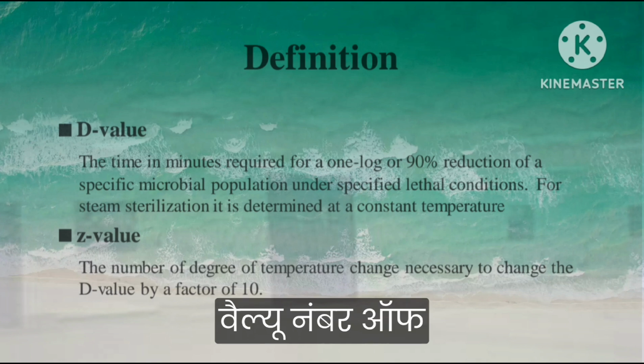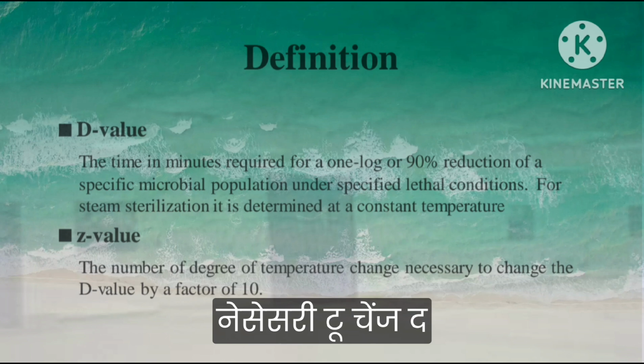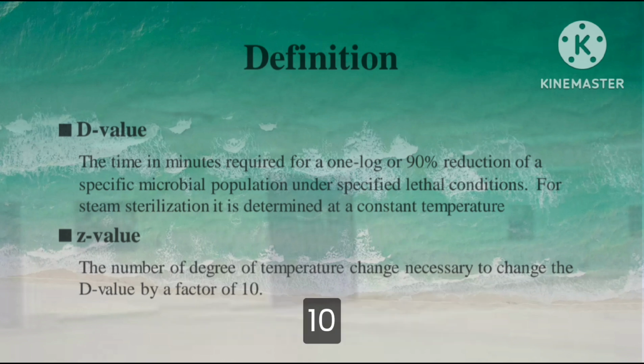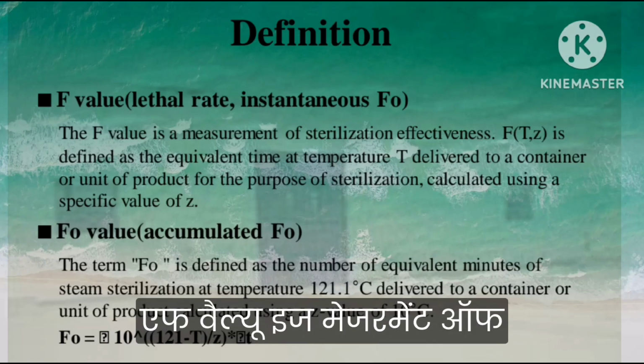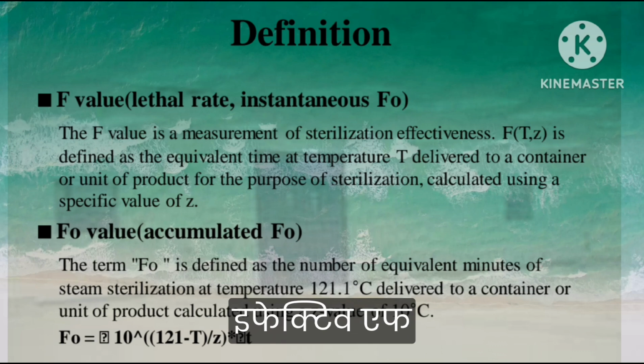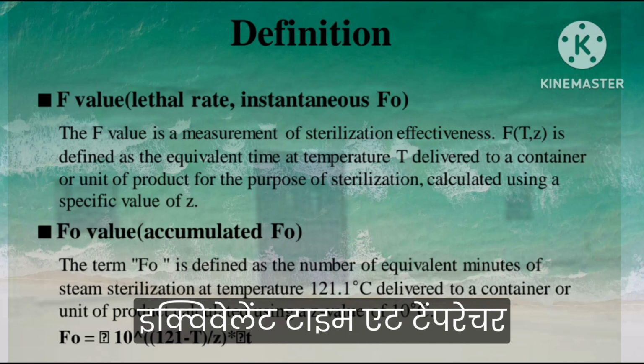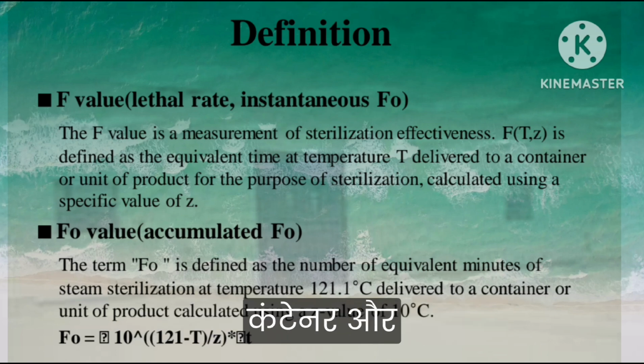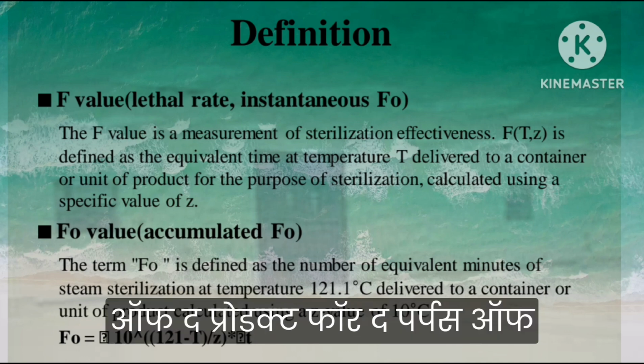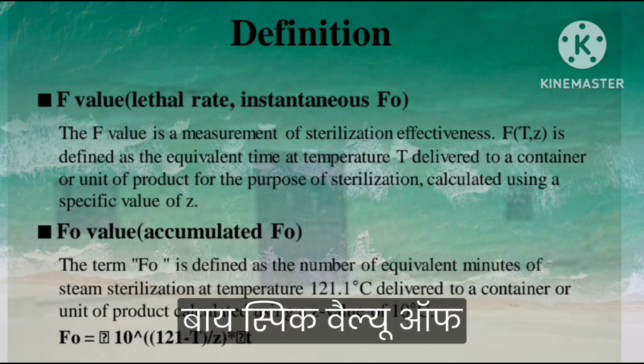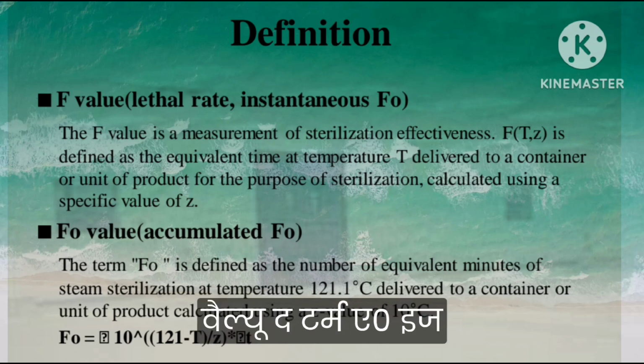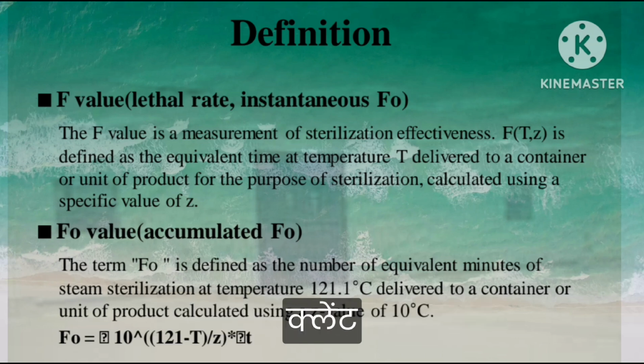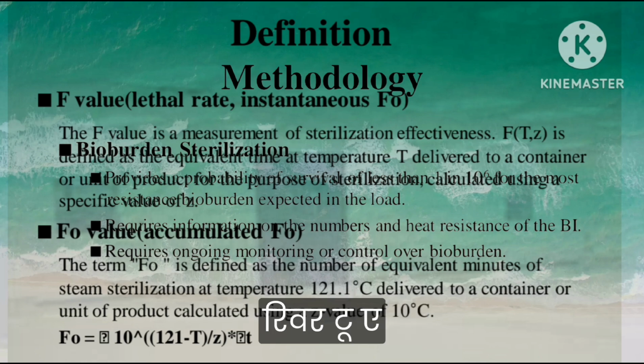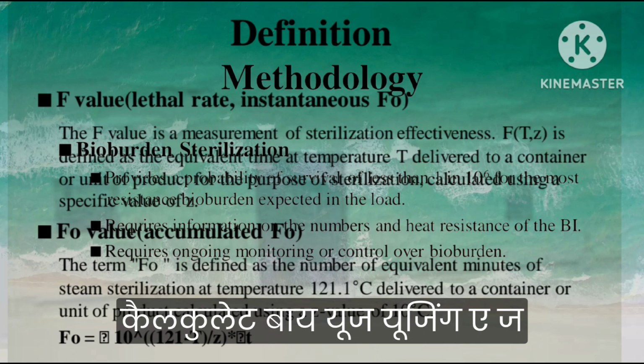Z value: the number of degrees of temperature change necessary to change the D value by a factor of 10. The F value is a measurement of sterilization effectiveness. F is defined as the equivalent time at temperature T delivered to a container or unit of the product for the purpose of sterilization, calculated using the specific value of Z. F0 value: the term F0 is defined as the equivalent minutes of the steam sterilizer at temperature 121 degrees centigrade delivered to a container or unit of product, calculated using a Z value of 10 degrees centigrade.